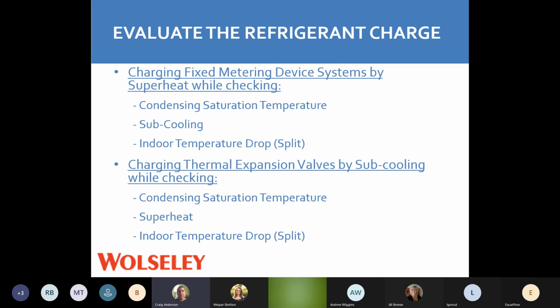So charging a fixed metering device system, superheat while you're checking. Your piston, we're doing it with superheat. We're checking the saturation temperature. We're also going to check our subcool too. We got our thermometers out there. We're going to check our superheat and subcooling. Doesn't matter if it's a TX or a piston. But if we're doing a piston, superheat is our temperature that we're going to use. Indoor temperature drop, which we call our split. So that's our temperature between our return and supply.